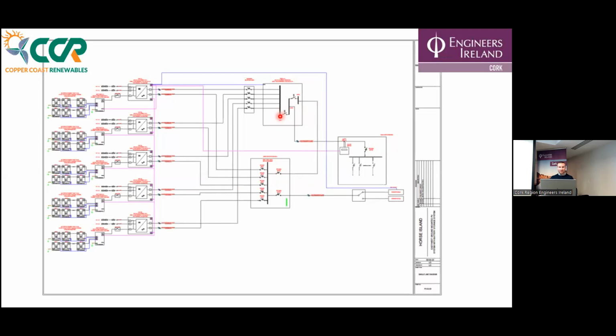It took a while to come up with the algorithm and wiring, but it works quite well, and it meant we didn't need to change the client's existing distribution board, just where it was fed from with our two new panels interlinked. We were also able to reuse the client's existing auto transfer switches. There's only one box shown here, but there's actually a second box in how it was wired on site, I just tidied it up for the presentation.